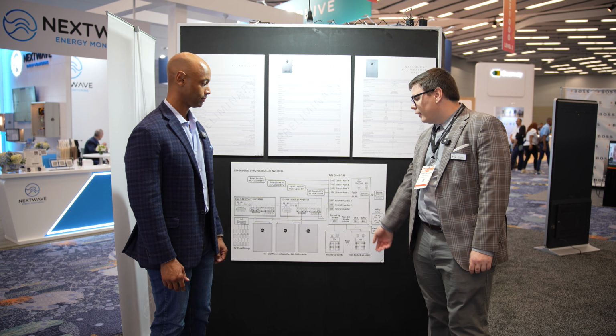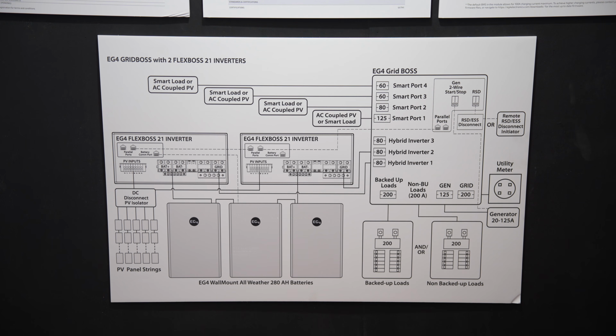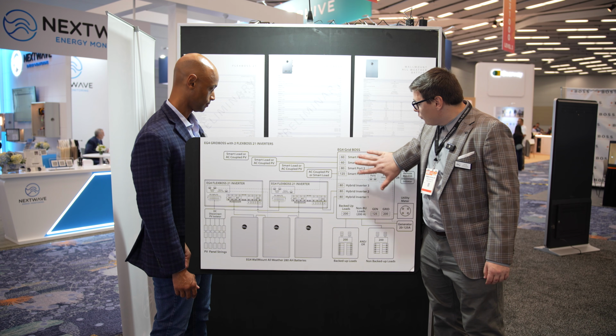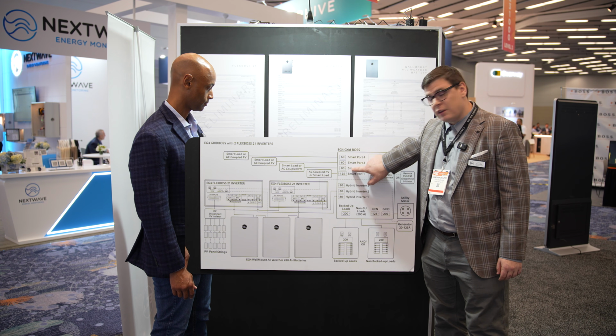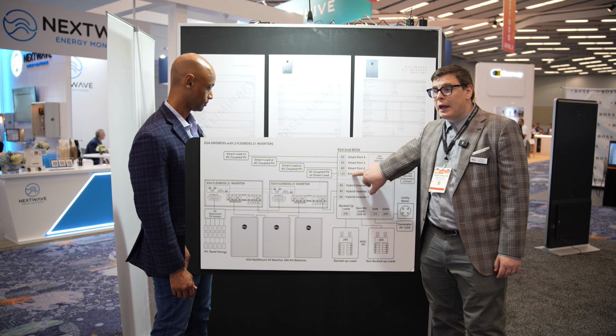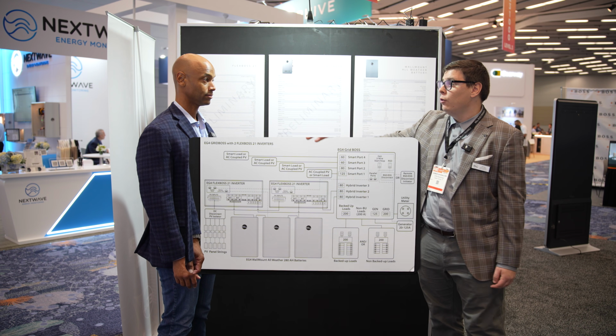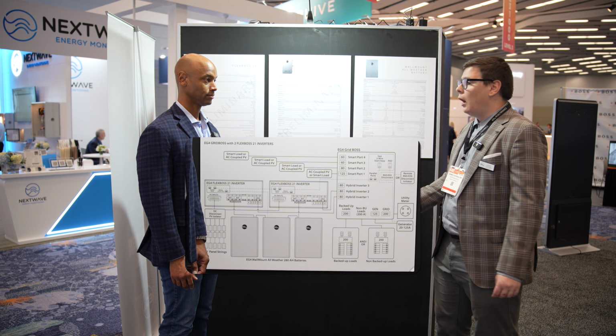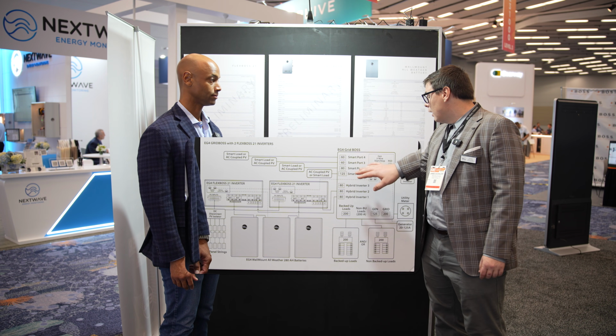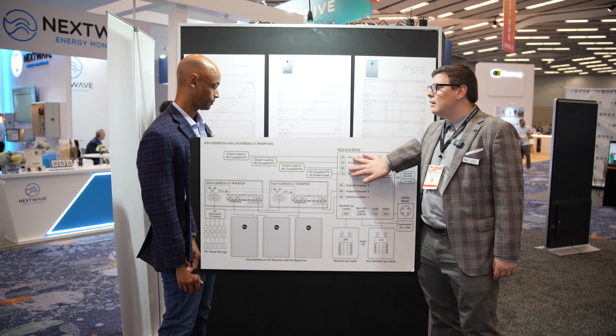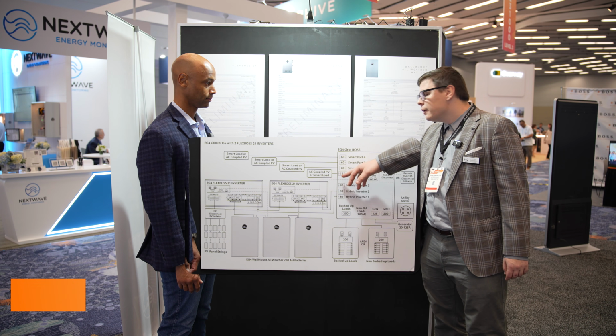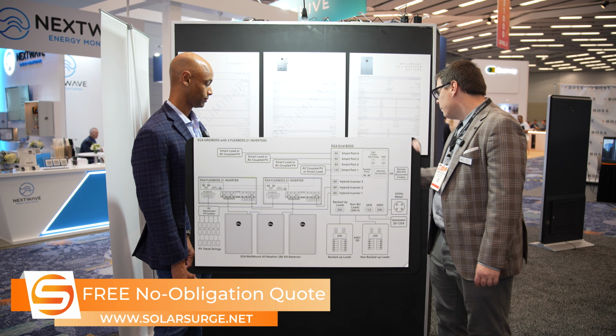Yeah, so this is exactly why I love that we came over here, because we designed the product by the single line diagram. How do we keep this simple for all the different problems people have? As you can see, this is drawn out. The smart ports, the 4 of them: you've got a 60, 60, 80, 125. Some people are going to have that 125 go to a sub panel for shed loads. You can use it for a lot of different things, so we have that on the top. Also, a lot of AC couple. You can get in 30 kilowatts of AC couple in phase if you want, right from that combiner panel. So use those whichever way you want to.